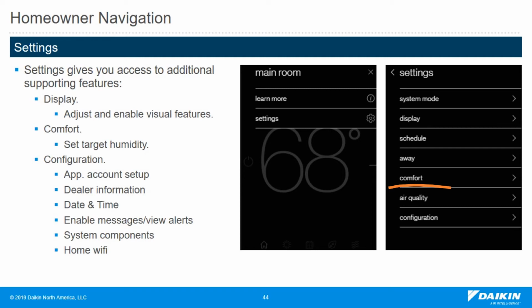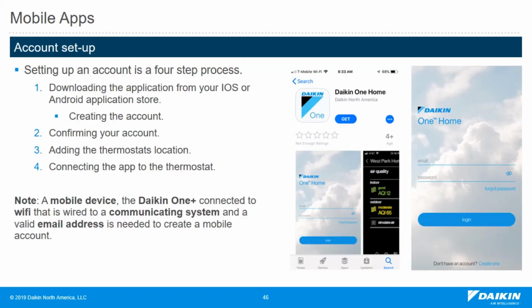The third one down is the schedule. It can also be done by using the icon. The away mode can also be done by using the icon. And the air quality can be done by using the icon. And the one I skipped there, the underlined one, is comfort. This is where they're going to enter to set the humidification and dehumidification level. So if you have a humidifier, this is where they'll set it. If you switch on the dehumidification function or you add an external dehumidifier, that's where you'll do the adjustment for the actual setting.